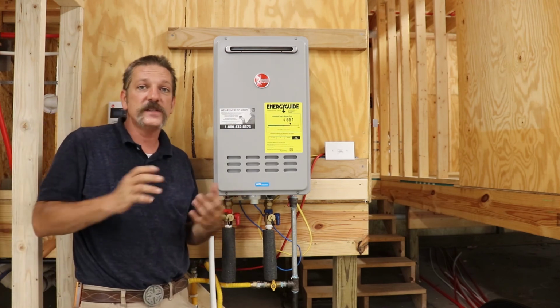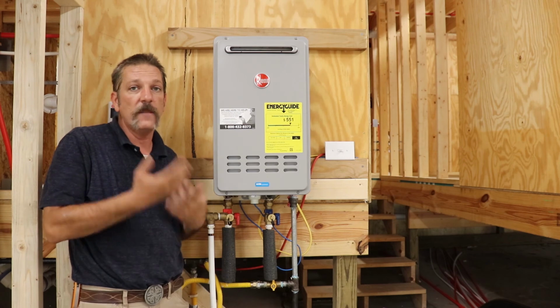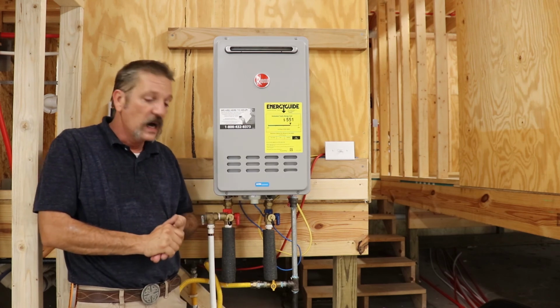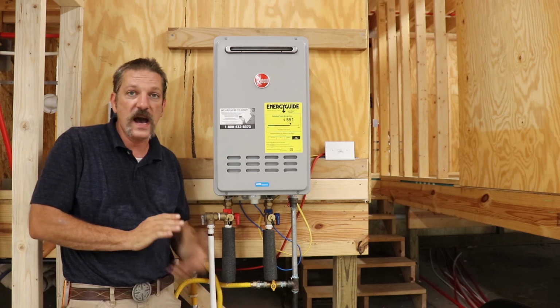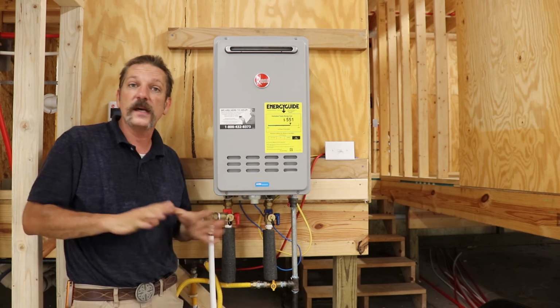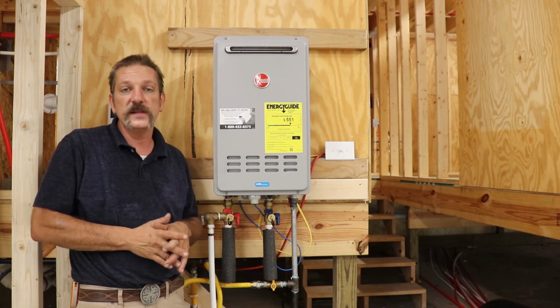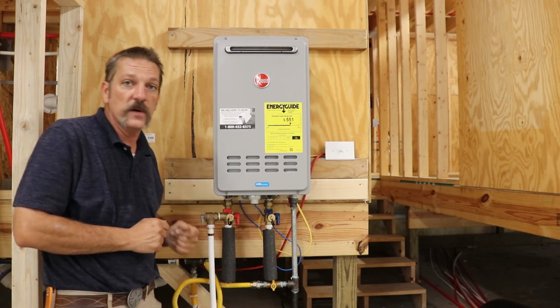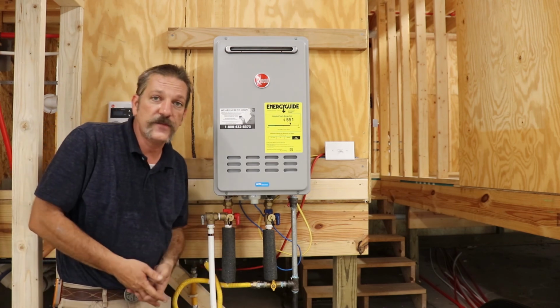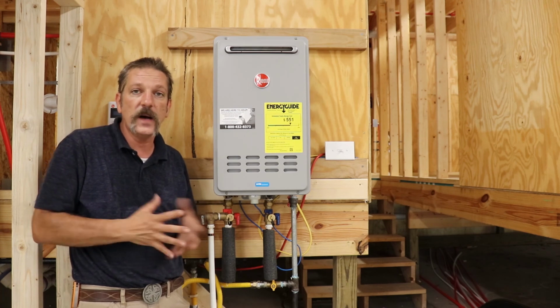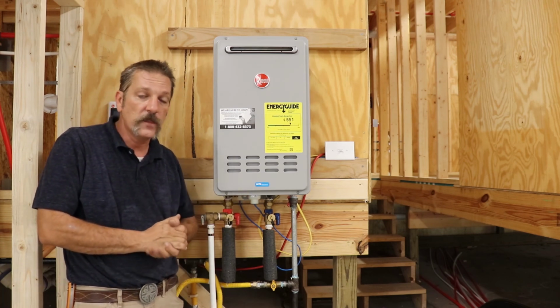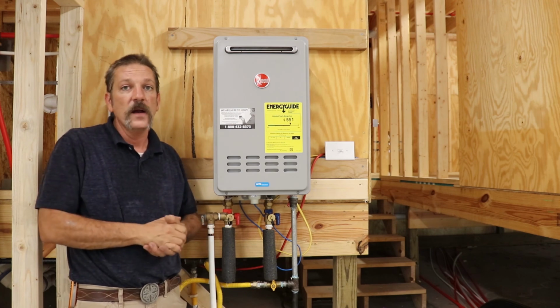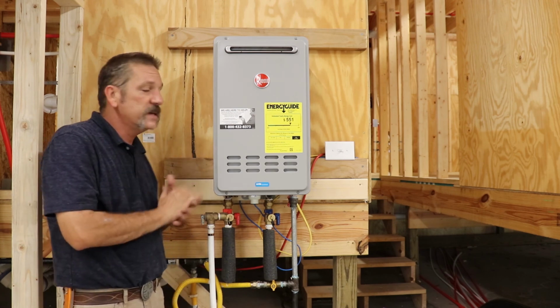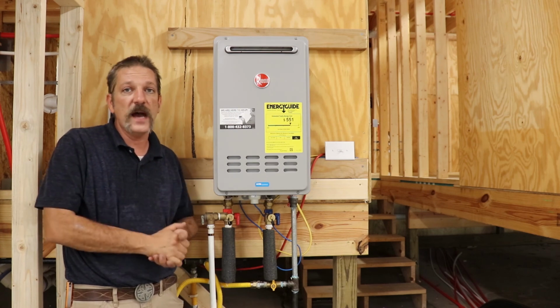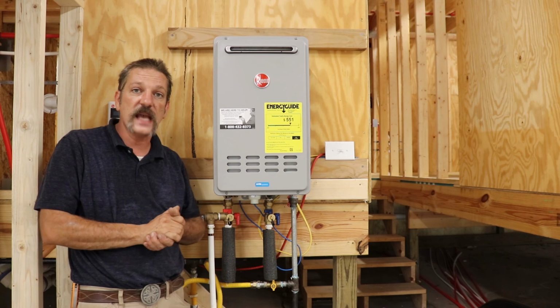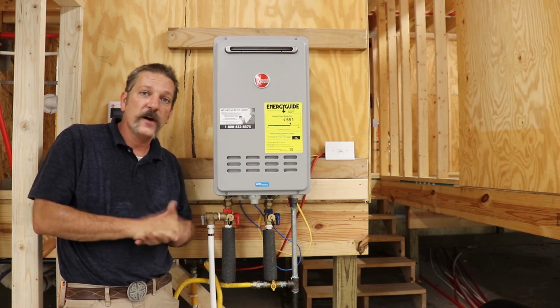Now, as a homeowner, if you want to descale your water heater, it's perfectly fine. Most manufacturers don't have a problem with you doing that. You can go to a plumbing supply house somewhere and buy these kits. Most of the time they have them right there on the shelf, and it comes with everything you need. They are a little expensive, but paying a plumber to come out and do this is a lot more expensive than that kit. Or you could just buy a 5-gallon bucket, go to the hardware store, get one of those little pumps that's meant for like a goldfish pond or something, and then just use white vinegar. But me as a plumber, if I'm selling this as a service, I'm going to use what the manufacturer recommends, and that is that descaling agent. So have fun and good luck out there.